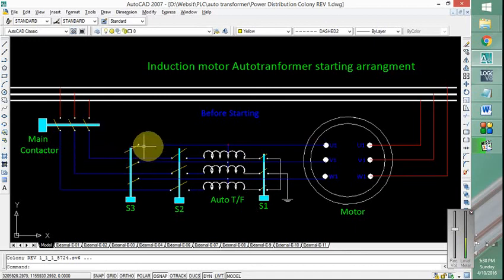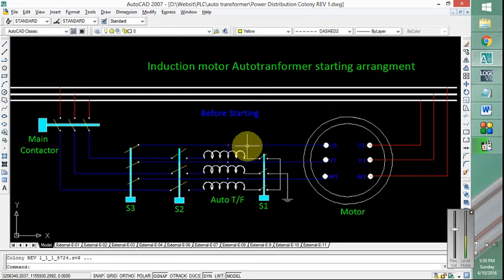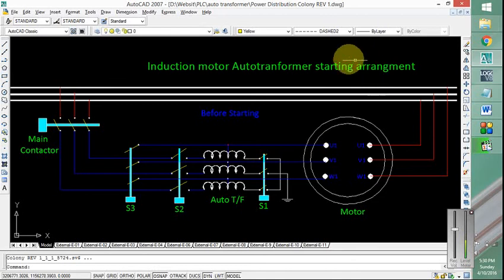So then the current will follow the path above the auto transformer, hence it will be bypassed and total voltage will be given to the motor. So in this way, a reduced voltage is given to the motor in the starting while full voltage is given when enough speed has been gained. Let us look at the PLC program and we will refer to it at different moments.